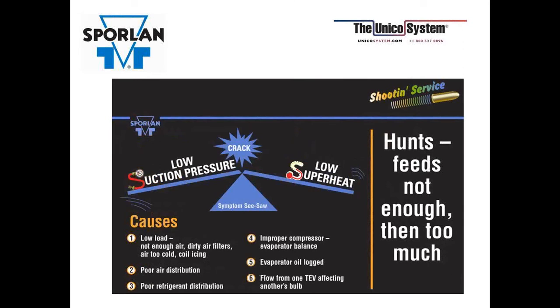And then next is hunting. We have a low suction pressure and low superheat. It's feeding too much, then not enough, feeding too much. It could be a low load situation where you're not having enough air. It could be dirty air filters. It could be poor air distribution, airflow again. Or it could be a poor refrigerant distribution issue. And that's where having the wrong size nozzle, the wrong size tubes can indicate that you're having a hunting issue problem.